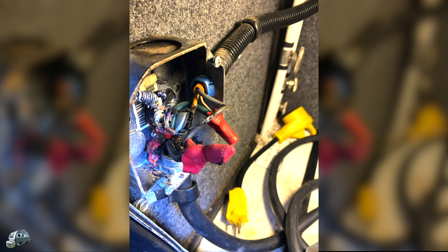I had assumed incorrectly that the 30 amp circuit breaker on our motorhome's power distribution panel limited the incoming power to 30 amps. It does not. A higher current will find the weakest link and cause damage, or worse.